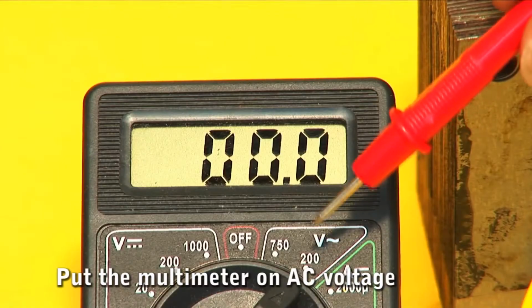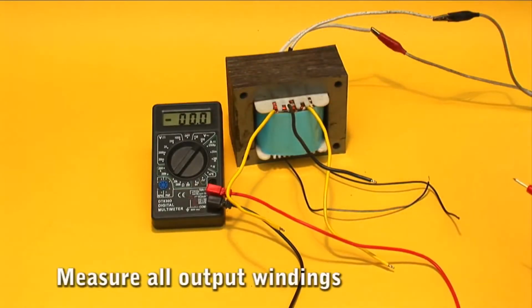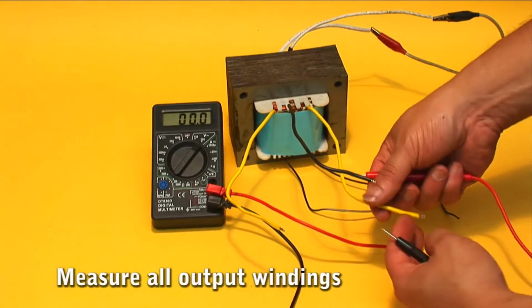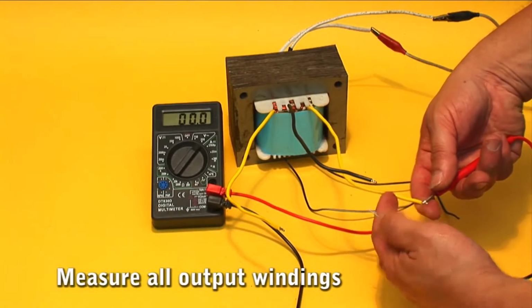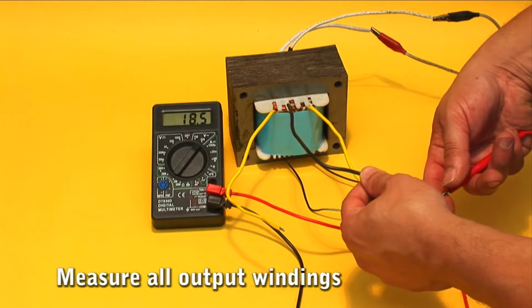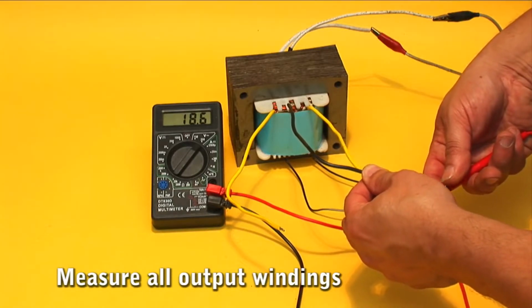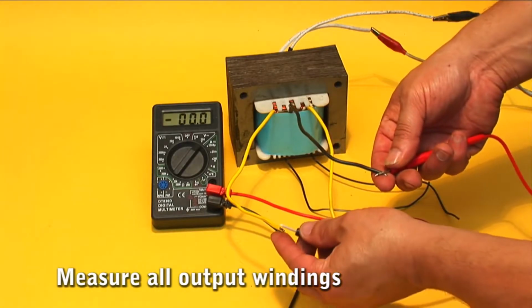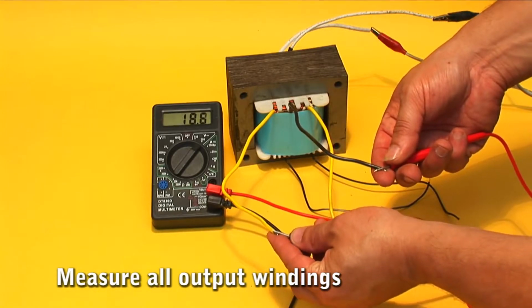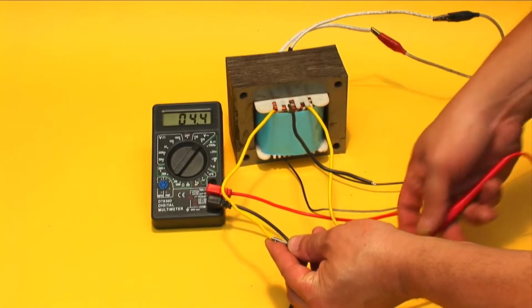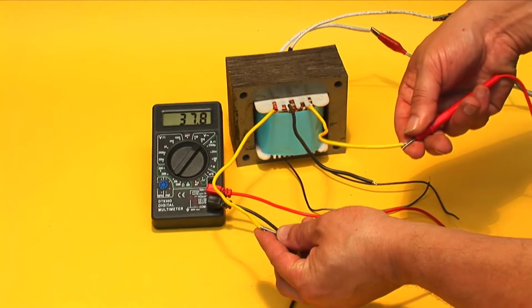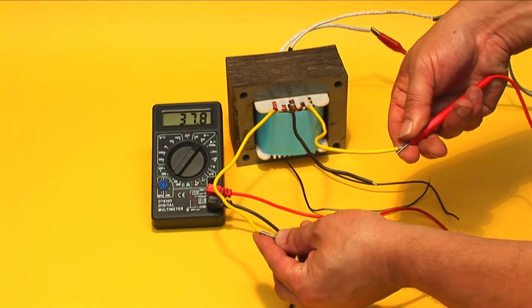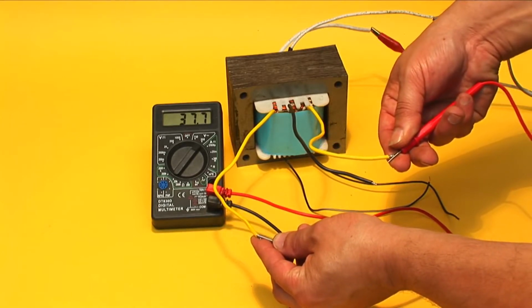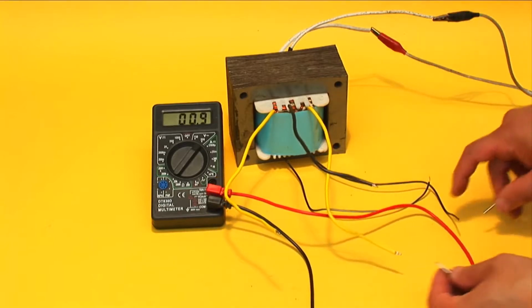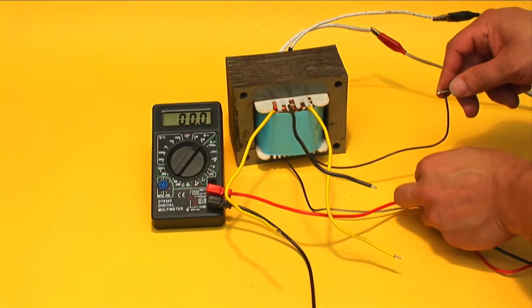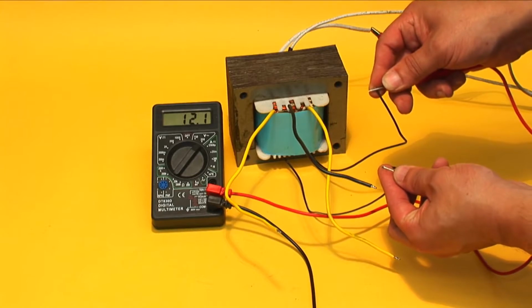With the multimeter on the AC voltage scale, place one end on the right end of the secondary winding and the other on the central tap. It should show the desired voltage, in this case 18 volts AC, as well as between the left end and the central tap. Measure between the two ends of the secondary winding. It should show twice that, in this case 36 volts AC. The additional winding must show the desired voltage, in this case between 12 and 13 volts AC.